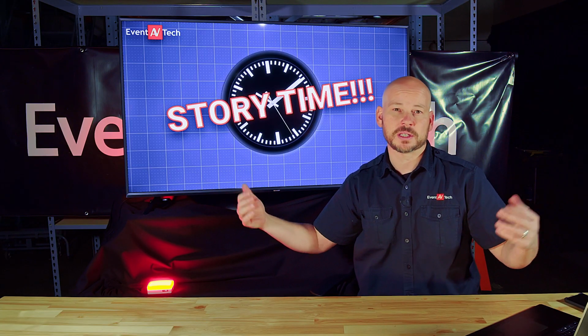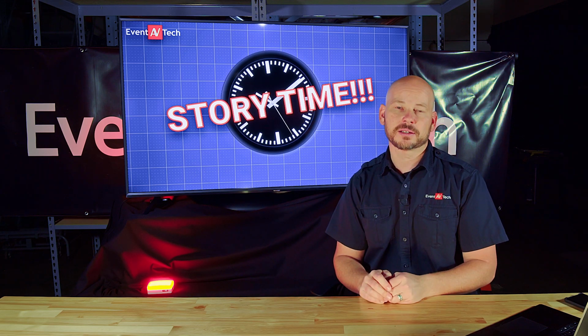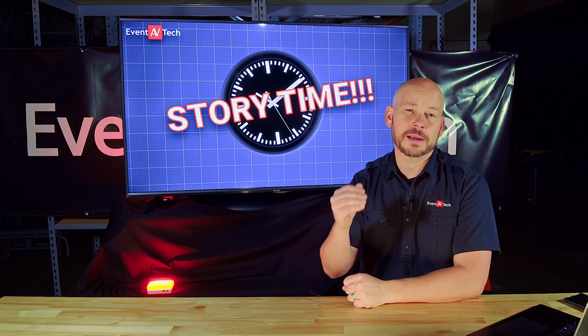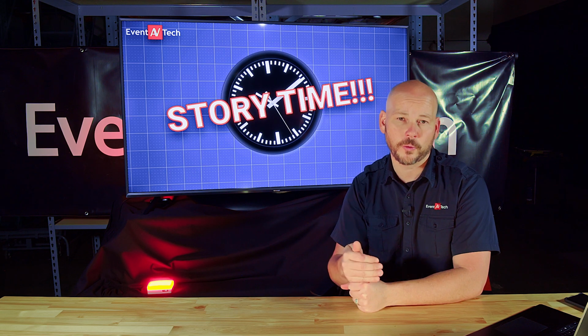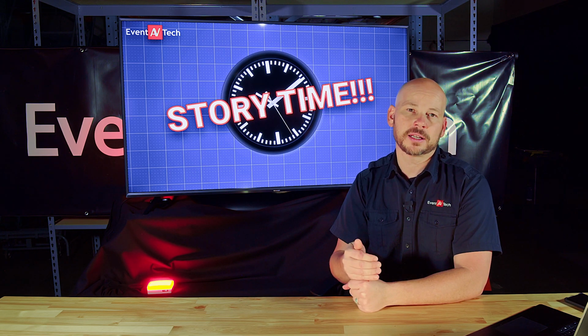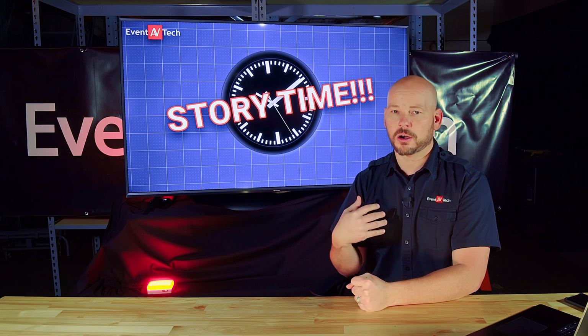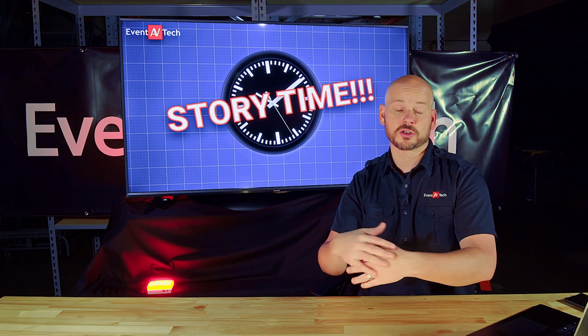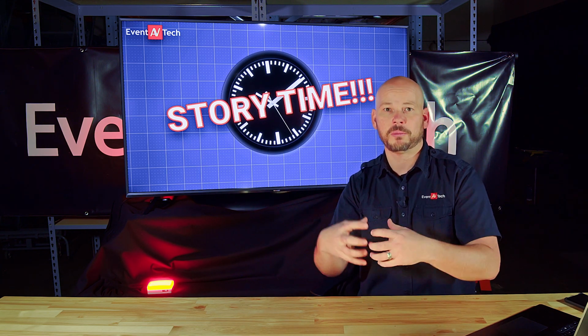Number one, we installed a large event space that had these huge, like 210 degrees of shades around the event space on motors. And in the pre-planning process, we had asked for an isolated AV panel, which means our audiovisual panel shares no power with anything else. It's all by itself in its own panel, and we got denied. And the trick that they used was a trick that I mentioned a little bit earlier in the video.